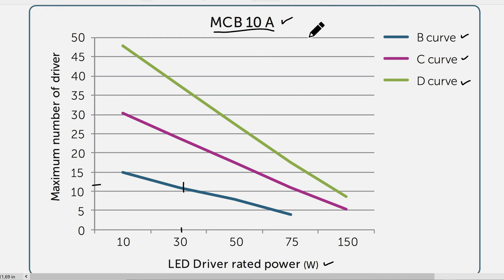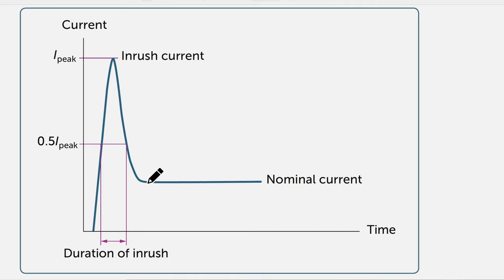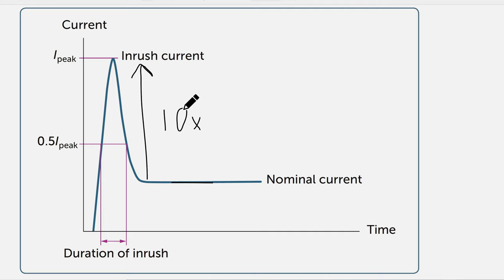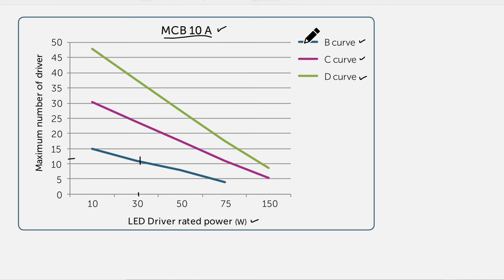The reason it would trip is because of the inrush current. If the inrush current is so much higher than the nominal current, every time I add a floodlight I have to account for that increase. If I have 10 floodlights, I will have 10 times the amount of inrush current. So one can see that it's the inrush current that is limiting how many floodlights we can use.